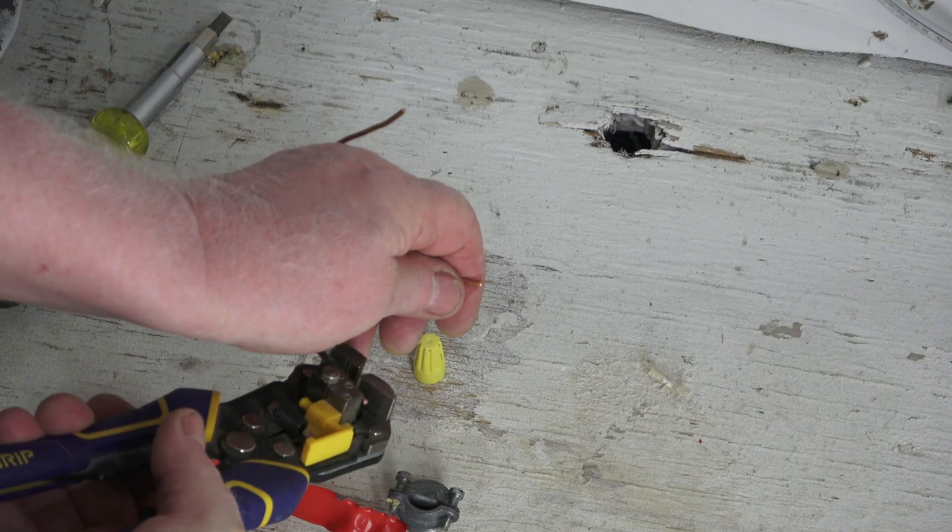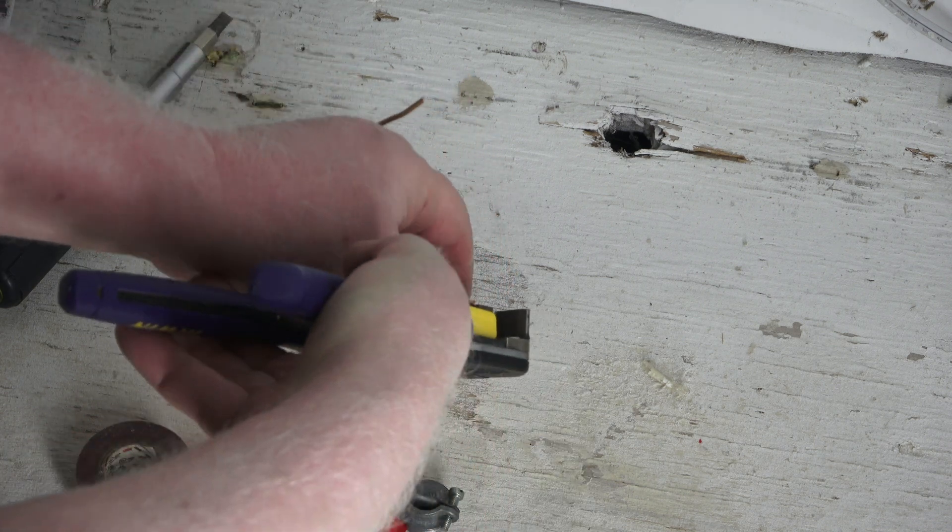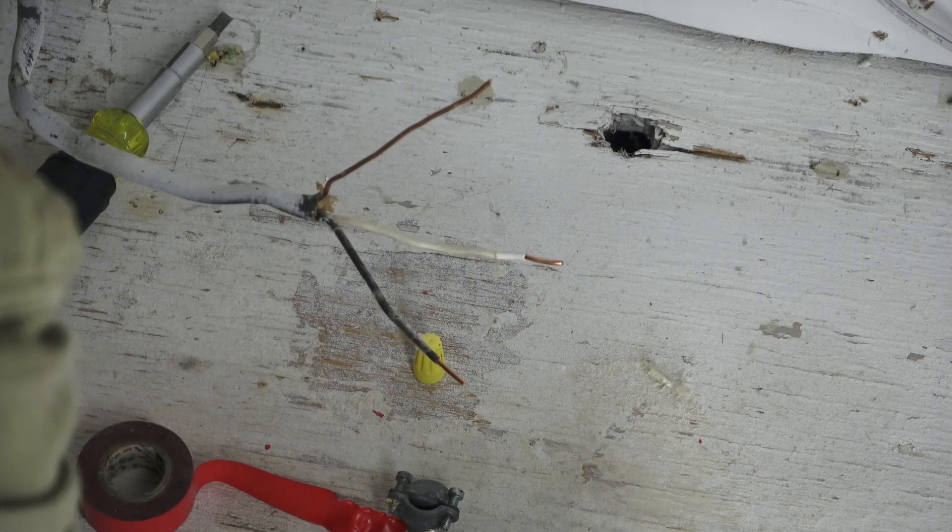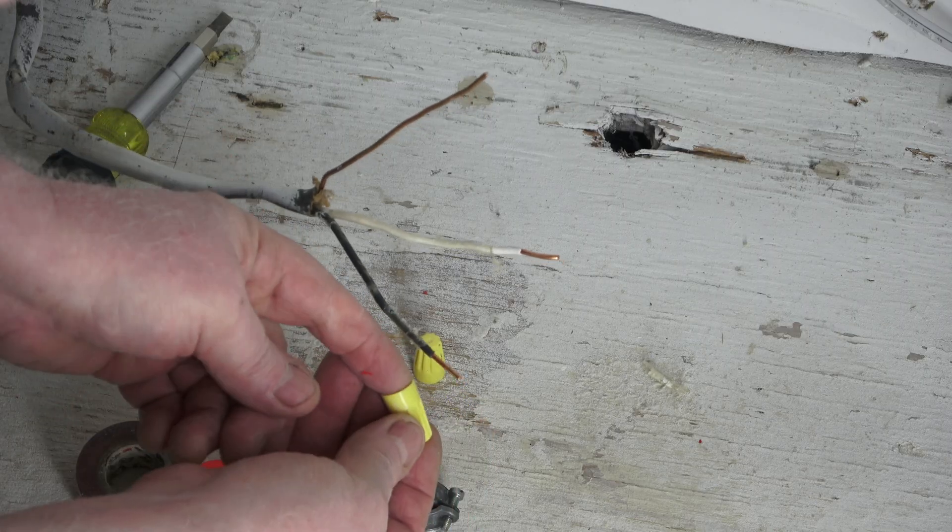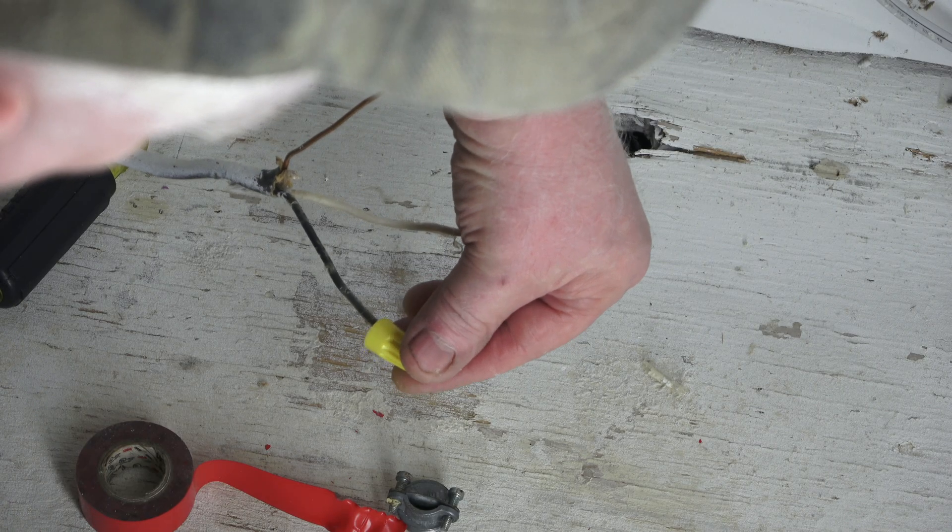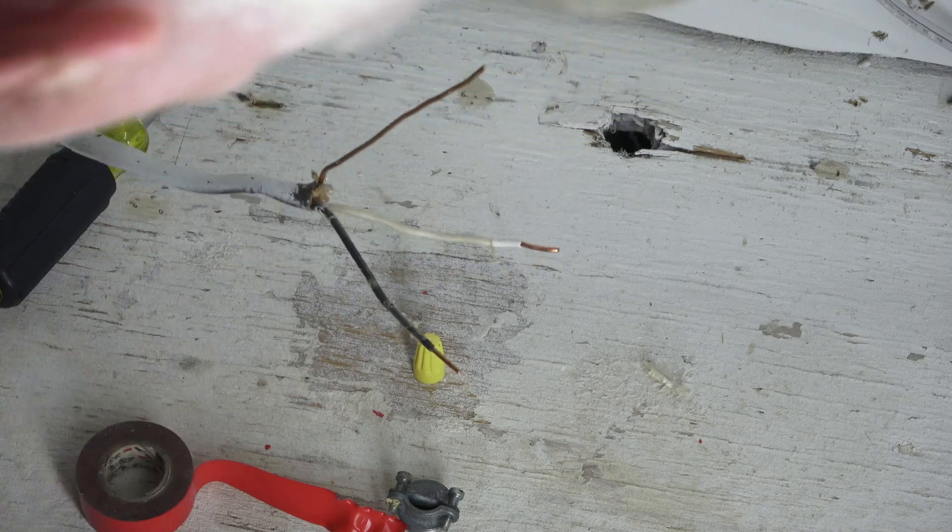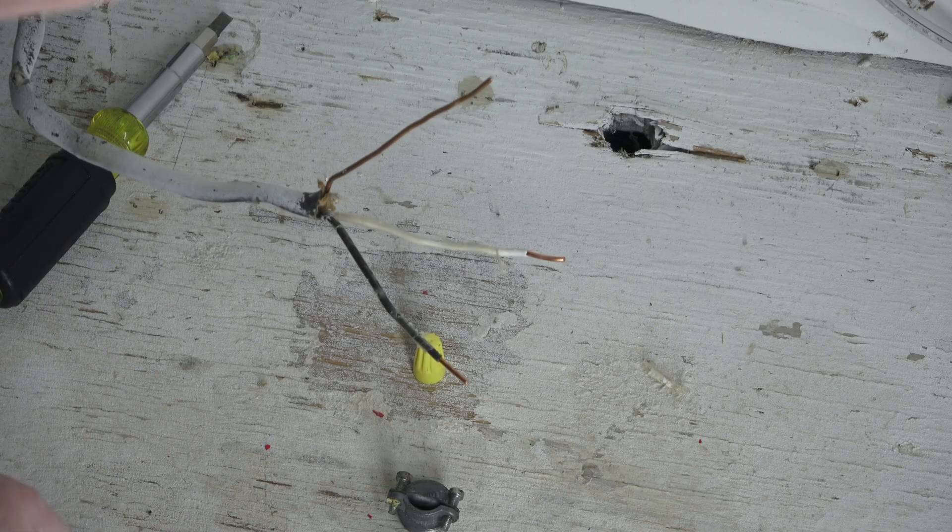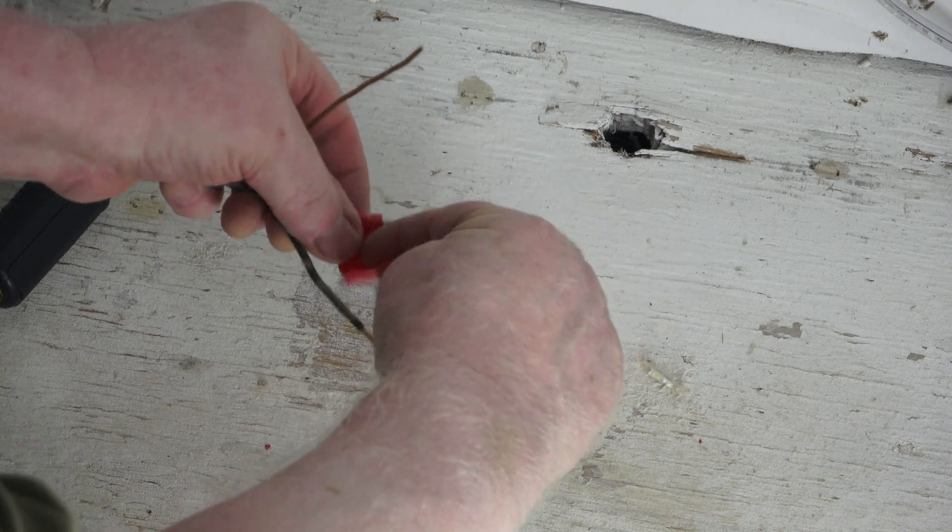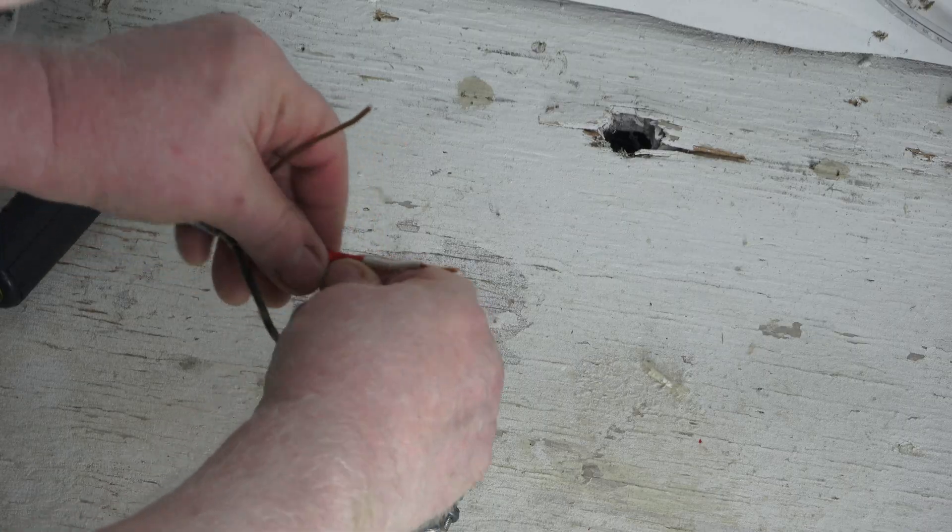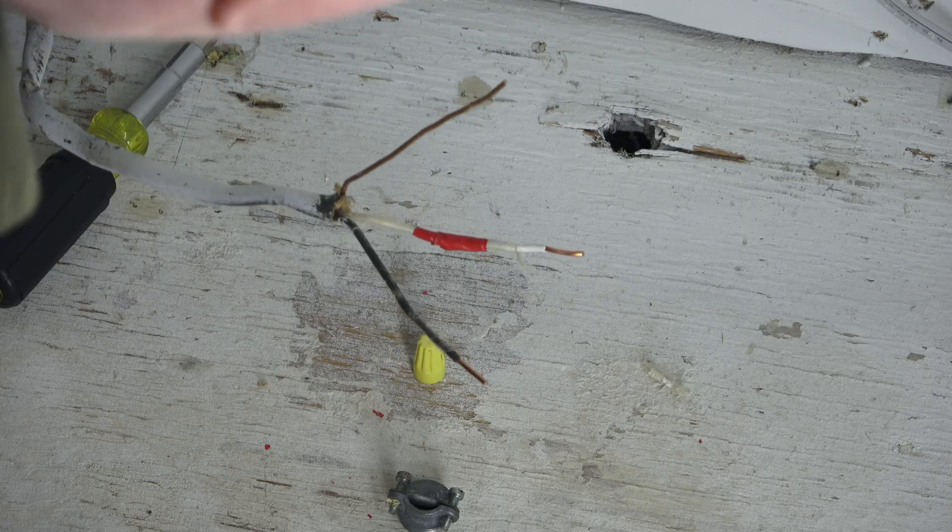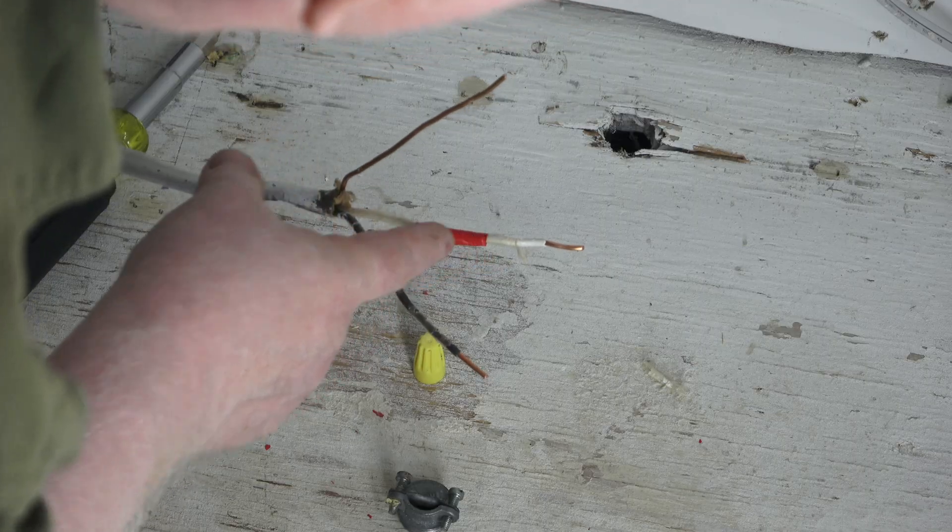So prep these wires. We want that bare wire a little bit longer. Nice. Now you don't want that any longer than your wire cap. You don't want any bare wire showing out the bottom of the cap. You can also tape them when we make the connection. I'm going to mark the wire. White wire with red. Today's wiring, more than likely, this would be red. Black. So I'm using red. But you can use black tape. That indicates that you're using this as a power wire. That way, if an electrician gets in here, he knows this is 120 on each leg. 240 combined.